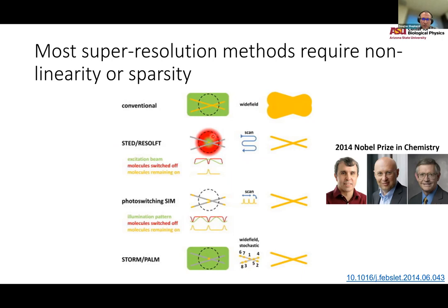That donut then makes all of the molecular reporters, which in this case are fluorescent molecules, undergo stimulated emission, so they're not seen at the same wavelength as the middle of the donut where you have normal emission. You then have to raster that donut beam plus the excitation beam around, and you would end up with this kind of image. So what I want to emphasize is it's a scan. And so this scan inherently is slow, maybe compared to the time dynamics you're interested in.